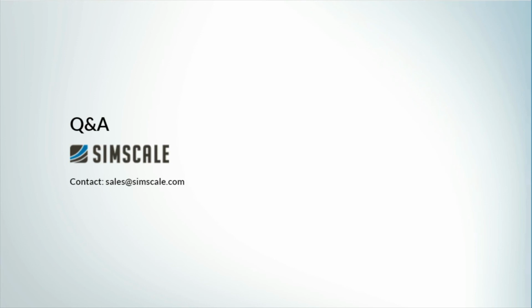There's another question. Why is the PMV high on the occupant's legs? That's a nice question. I did mention while doing this setup that we have these heat generating elements modeled into the simulation. Right next to the legs, there were heat generating computers or PCs. So the local temperature there is different than the other temperatures. This might create a difference in the PMV values near the legs.